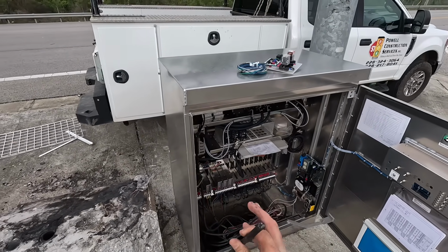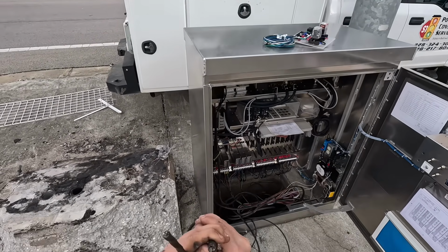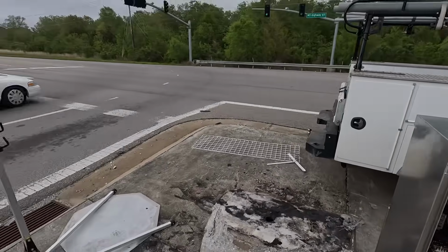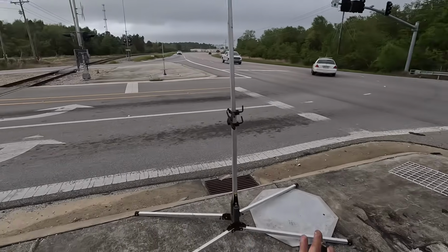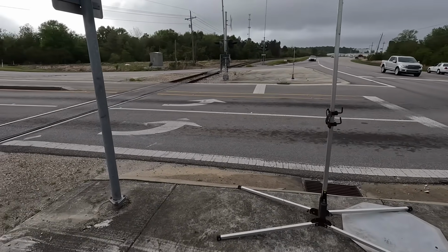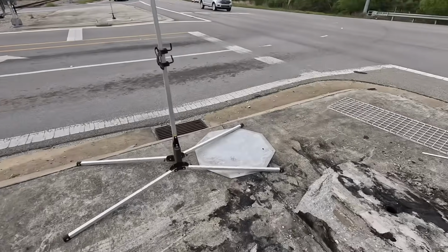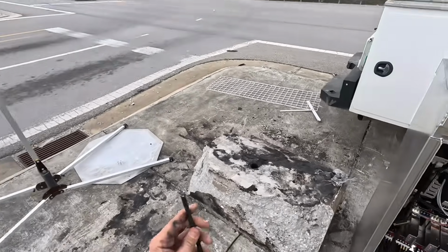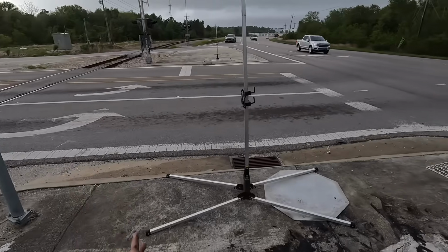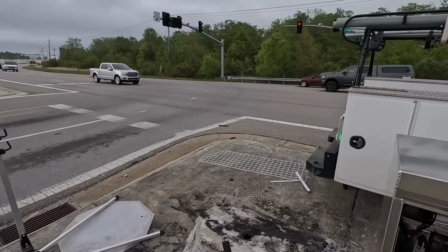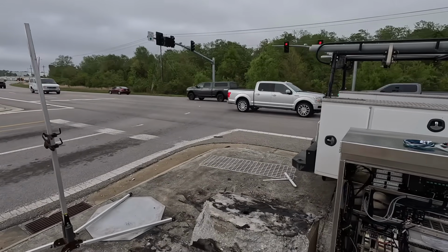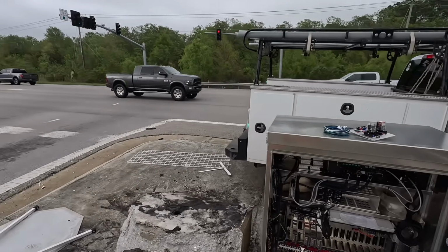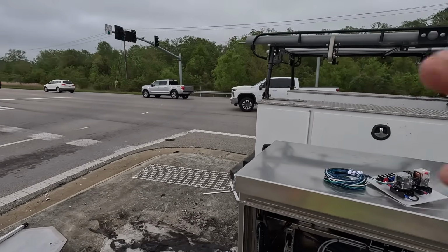Now, one of these two conductors, this looks to be a number 10, a two conductor number 10. I would imagine that would be going to the LED blank out, since everything on their side should be low voltage. And this two conductor looks like a number 12 or 14. This would be going to the railroad side. But to verify that, I can go over to that pole over across the street with the blank out sign, uncover the manhole, and figure out which two conductors are running to it.